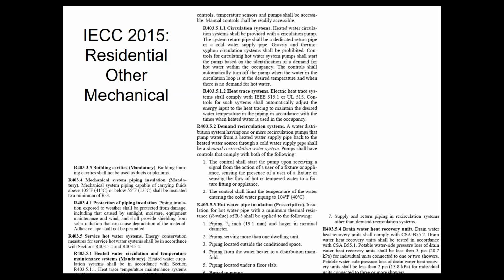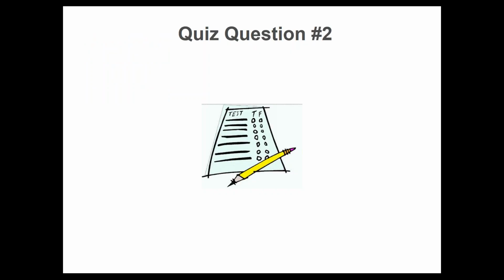You cannot use wall cavities or ceiling areas as your ducting means, right? So you can't use any building cavities, drywall, wood; your ductwork cannot be made out of those things. There's requirements for insulating pipe systems, right? And then after that, we're really done with residential HVAC. There's other stuff on this page that applies to mechanical systems, but not really HVAC. Everything else on here would apply to domestic hot water, which is a whole separate discussion, if you will.